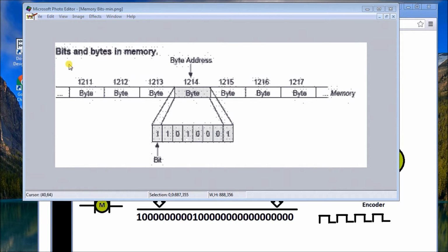Now if we look up here, everything boils down to bits in the PLC, and the bits are either one or zero, and usually you have an address associated with that bit, which determines the spot in which you can pick it up. And again, for addressing, we look at the PLC itself. We can have direct addressing or indirect addressing, which will allow us to either look directly at that register for the information, or we use what we call a pointer, and the pointer will tell us the location in which to look to get that information.